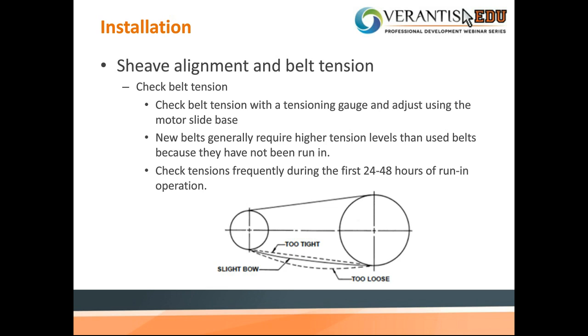New belts typically require a higher tension level than used belts. This is simply because the belt hasn't been run in yet. But definitely check the tension frequently during the first 24 to 48 hours of run-in operation, because it will change over a period of time. When you're doing routine inspections of the fan, you definitely want to always check the tension. The picture below shows if it's too loose or too tight and where it should be.